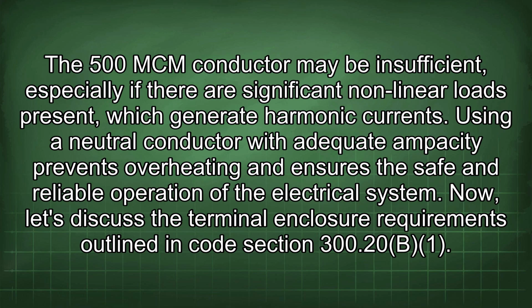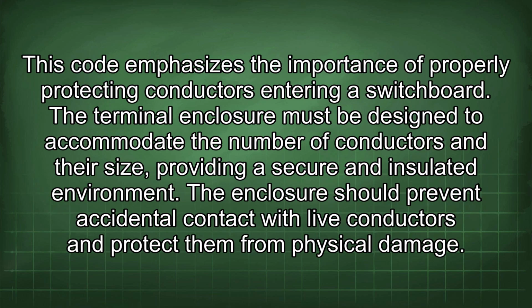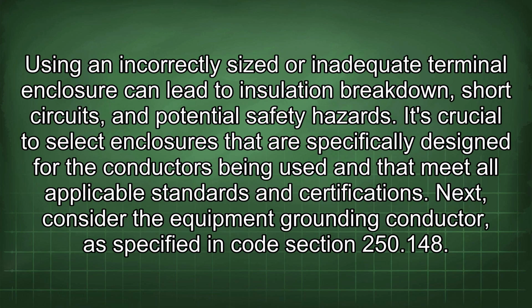Now, let's discuss the terminal enclosure requirements outlined in Code Section 300.20. This code emphasizes the importance of properly protecting conductors entering a switchboard. The terminal enclosure must be designed to accommodate the number of conductors and their size, providing a secure and insulated environment. The enclosure should prevent accidental contact with live conductors and protect them from physical damage. Using an incorrectly sized or inadequate terminal enclosure can lead to insulation breakdown, short circuits, and potential safety hazards. It's crucial to select enclosures that are specifically designed for the conductors being used and that meet all applicable standards and certifications.